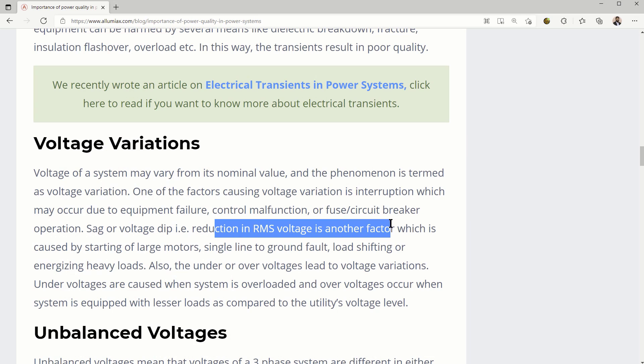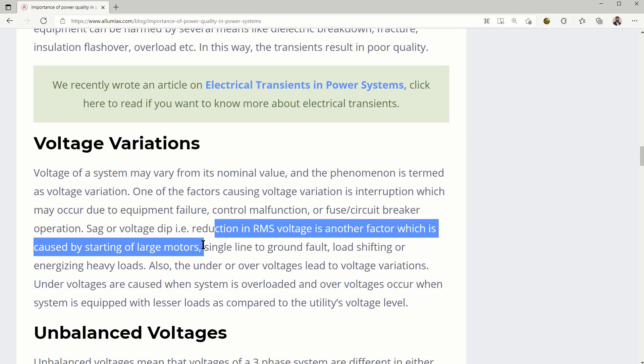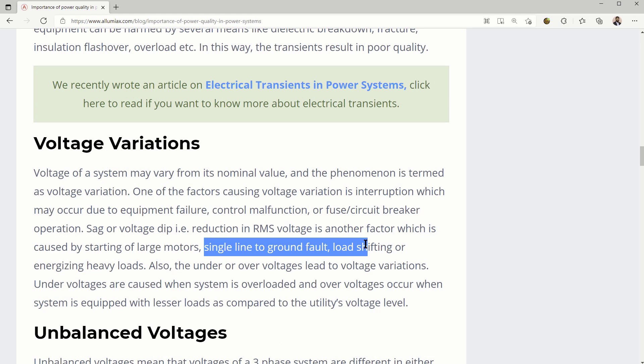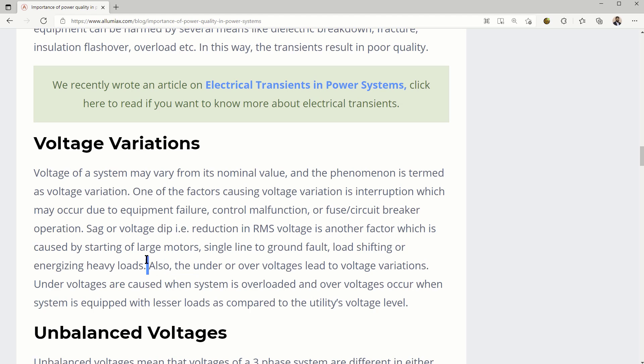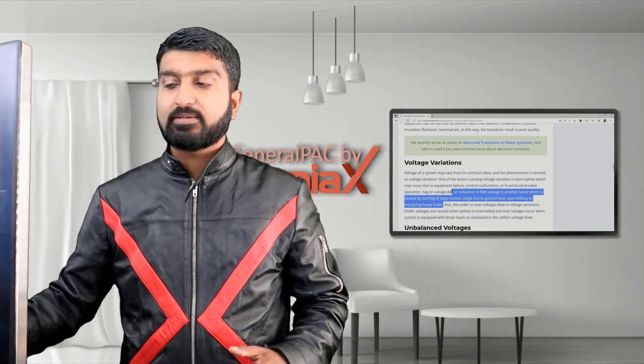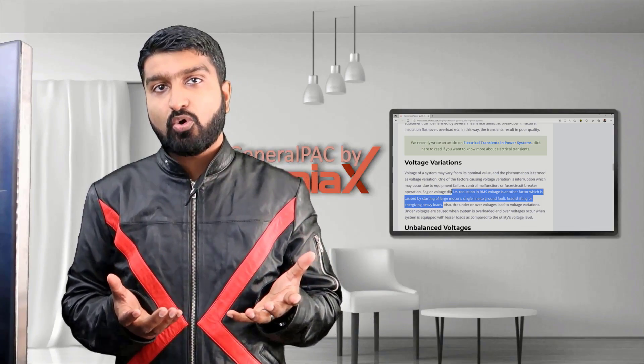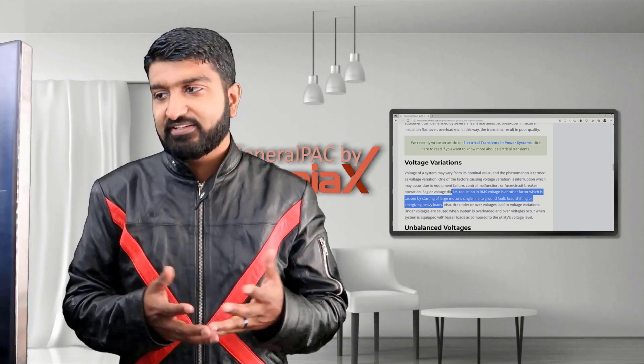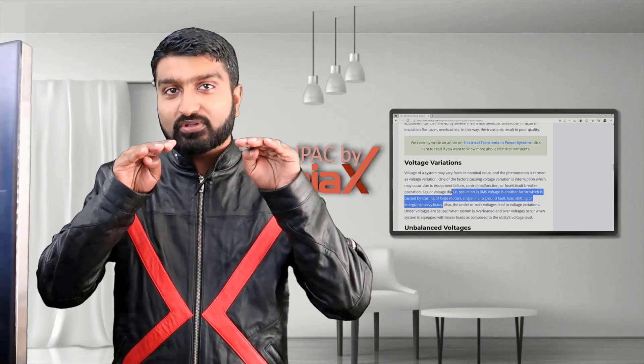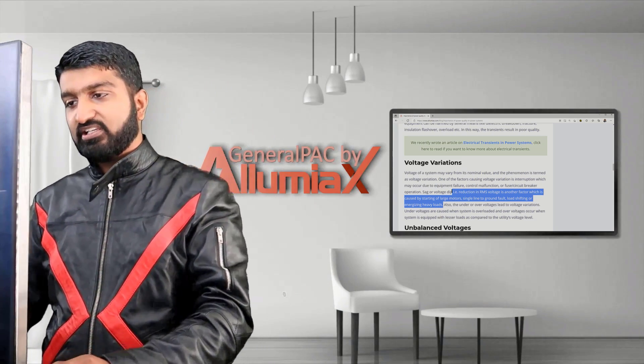Reduction in RMS voltage is another factor, which is caused by starting of large motors, single line to ground faults, load shifting, or energizing heavy loads. This also makes sense — in an industrial plant, or even like a compressor at home or a microwave, as soon as we turn on that heavy powered equipment, sometimes we see our lights kind of dim down and then come back up, and that's what we mean here.